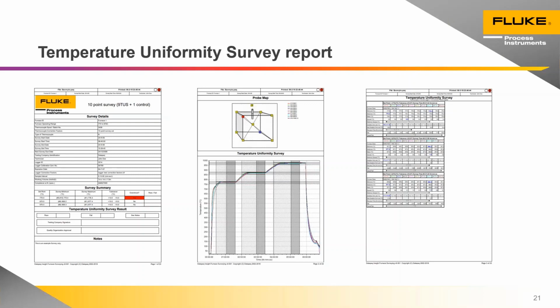Second page, you can see what's here, the probe map. In addition, just to the right of it, a bit small to read, are the probe descriptions. So this would probably be serial numbers of the probes used. I would suggest that's the best way of doing it, so that you can always relate back to the calibration files that you've got for those thermocouples. Uniformity survey results, that is what it is.